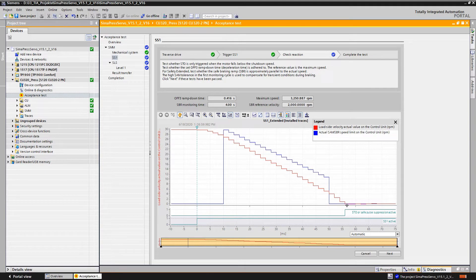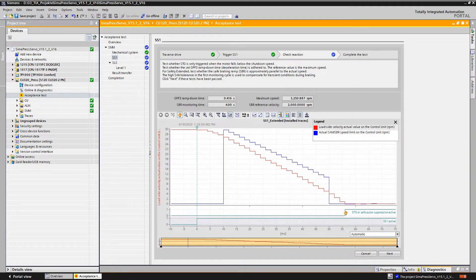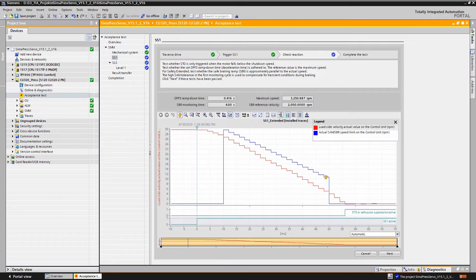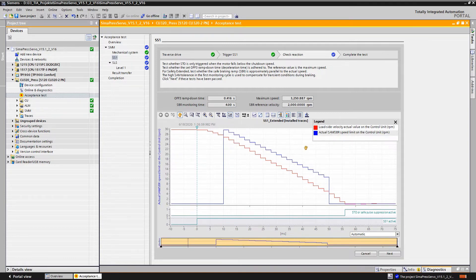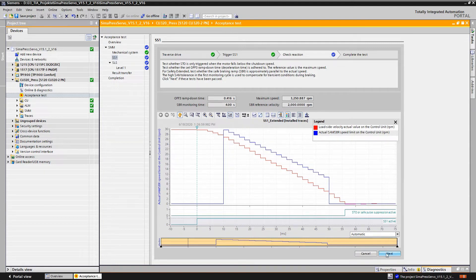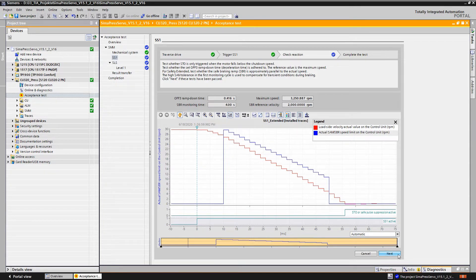We also check whether the follow-up reaction STO trips approximately after reaching a standstill, in other words, not too early and not too late, and whether the safe brake ramp monitoring shown here in blue is correctly set, in other words, approximately parallel with the braking ramp.